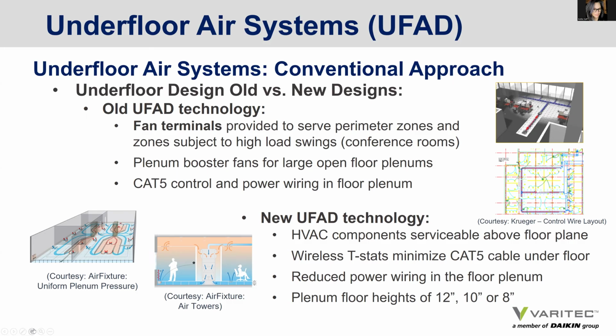New UFAD technology, however, is completely different. No mechanical device is now required that requires floor access, moving floor terminals or floor tiles. Devices can be serviced directly from the floor side. You don't have to remove tiles. There's minimal wiring, Cat5 cabling, due to wireless thermostats being available in the industry today. Minimum power wiring to do that. So this is pretty attractive now that the service of UFAD system equipment is no longer necessary by removing floor panels and getting under the floor to actually work on components.